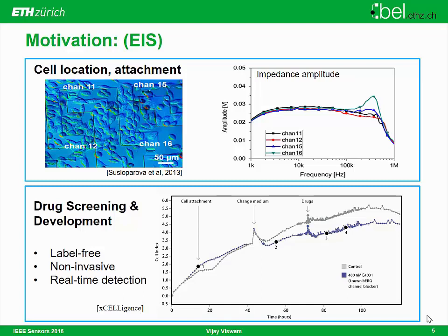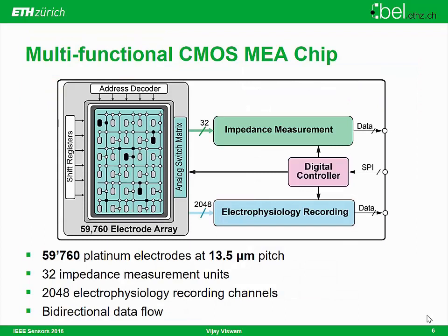In this application, spatial resolution has been limited in previous work, so we are focusing on high-density integration of impedance sensors on the chip. In our case, we integrated around 60,000 electrodes on a CMOS-based microelectrode array with a pitch of 13.5 micrometers. There are 32 impedance measurement channels integrated on-chip and 2,048 electrophysiology channels also integrated on the same chip. These channels can be connected to any of these electrodes arbitrarily through an analog switch matrix configuration developed in our lab.